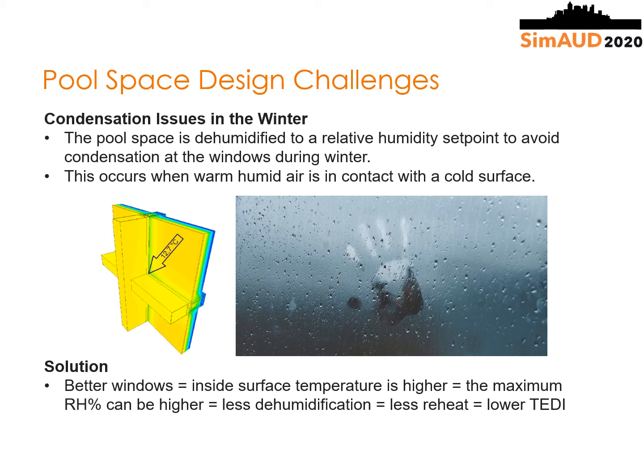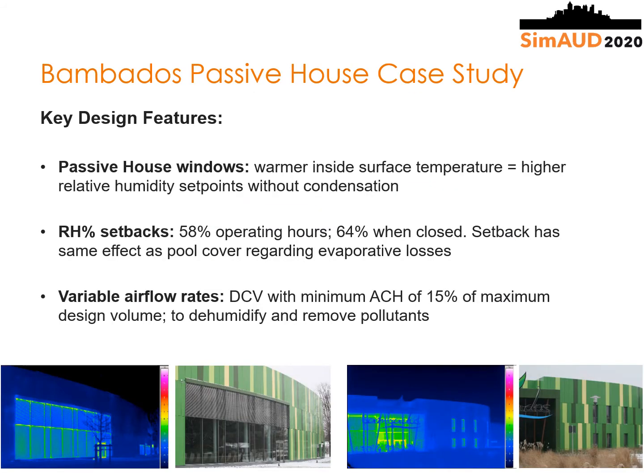But another solution is to provide better windows. So if you have better windows, the inside temperature is higher and the maximum relative humidity percentage set point can be higher, which leads to less dehumidification, less reheat, and a lower TEDI value. So we looked at some passive house pools to see how they reduced their TEDI value.